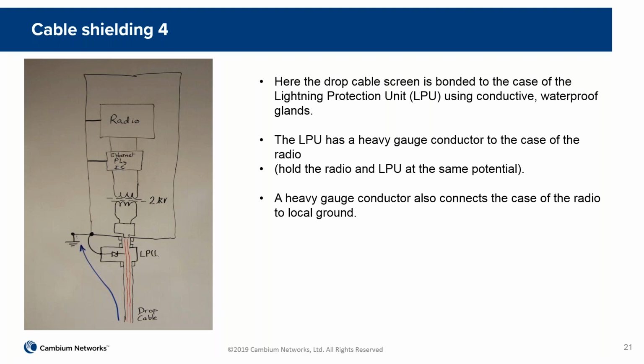So here we've brought it all together. Our drop cable is screened. It connects directly to our LPU via a gland which causes the current to flow from the screen into the body of the LPU and then through the grounding cable to the radio and ground. And we have a good bond between the LPU and the radio itself on the screen, and the cores are carried through into the radio. The LPU has ensured that the cores don't have a voltage which exceeds the 2 kV withstand voltage of the radio, and actually is more of the order of 100 to 200 volts.